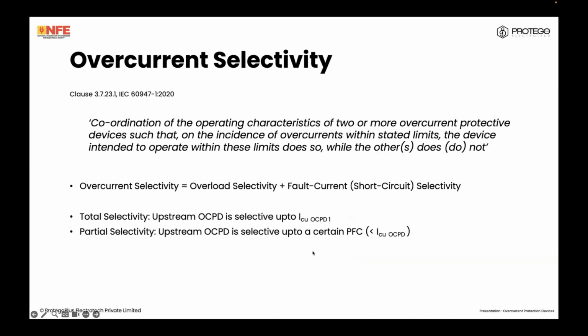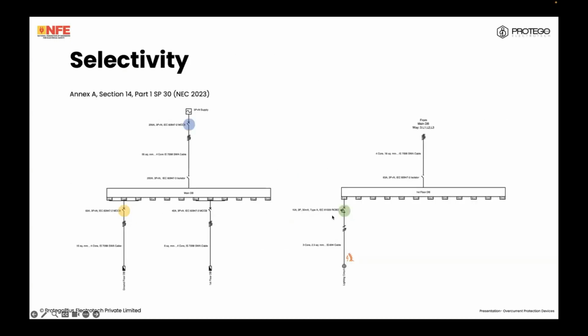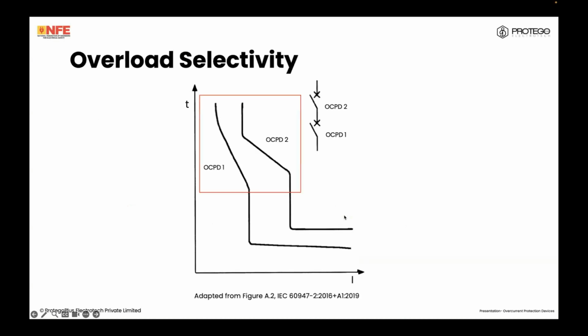So when you say total selectivity, it's only up to Icu, the ultimate short circuit breaking capacity of the immediately upstream protective device. How we achieve overload selectivity is very easy. We compare the thermal part, essentially the long time part, of the two overcurrent protecting devices.